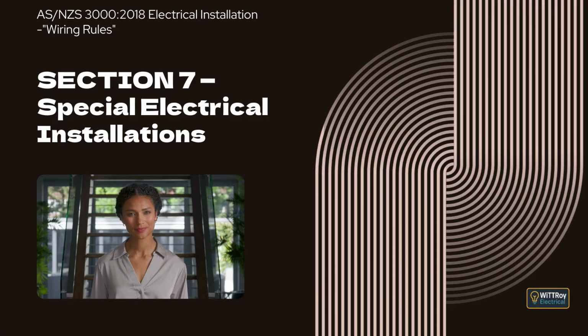Clause 7.2.2.1 General. This clause reinforces that wiring systems associated with safety services must be selected and installed so that they can maintain supply under fire conditions, and that the integrity of the supply takes priority over normal electrical loads. Clause 7.2.2.2 WS classification is not provided. This clause explains what to do when a relevant standard does not specify a wiring system classification.